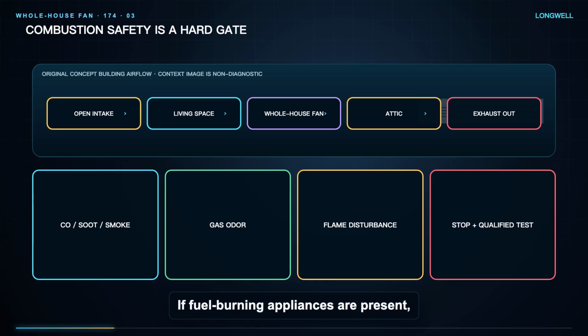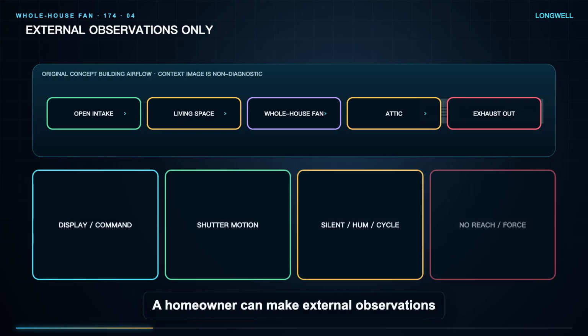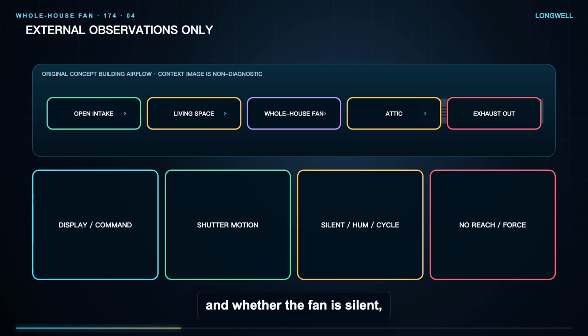If fuel-burning appliances are present, or you notice a carbon monoxide alarm, soot, smoke, flame disturbance, gas odor, dizziness, or unusual depressurization, stop. Move to safety and use qualified combustion and ventilation assessment before operating the fan again. A homeowner can make external observations without entering the attic or removing guards. Note whether the controller displays power, whether a command is accepted, whether shutters move, and whether the fan is silent, humming, cycling, or producing airflow. Do not reach through a grill or force a shutter.